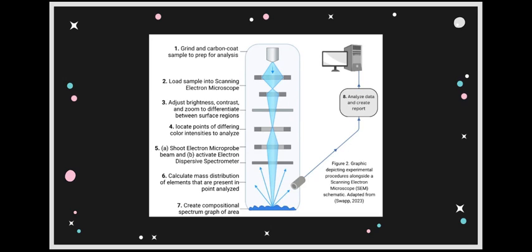Then I can use energy dispersive X-ray spectroscopy, or EDX, to analyze the composition of any point on the surface of a sample. EDX sounds really fancy, but it's honestly pretty simple. Basically, I shoot a point with a high energy electron beam that knocks valence electrons out of their shells and replaces them. Since there's a discrepancy between the electron energy levels and that energy has to go somewhere, an X-ray is released, and this X-ray can be measured to determine what atom the interaction took place in.